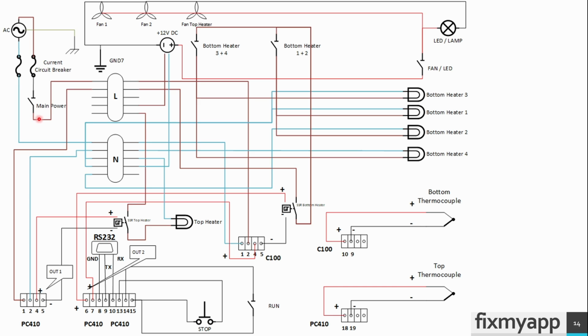From the main switch there will be a connection to this terminal block, the phase terminal block, and it will power all those connections. The phase and neutral line will go to the temperature control, the PC410, to power this temperature controller, and it will only power this up when this power switch is turned on. The same applies for the REX-C100 temperature controller. The neutral line and the phase line will power this temperature controller.